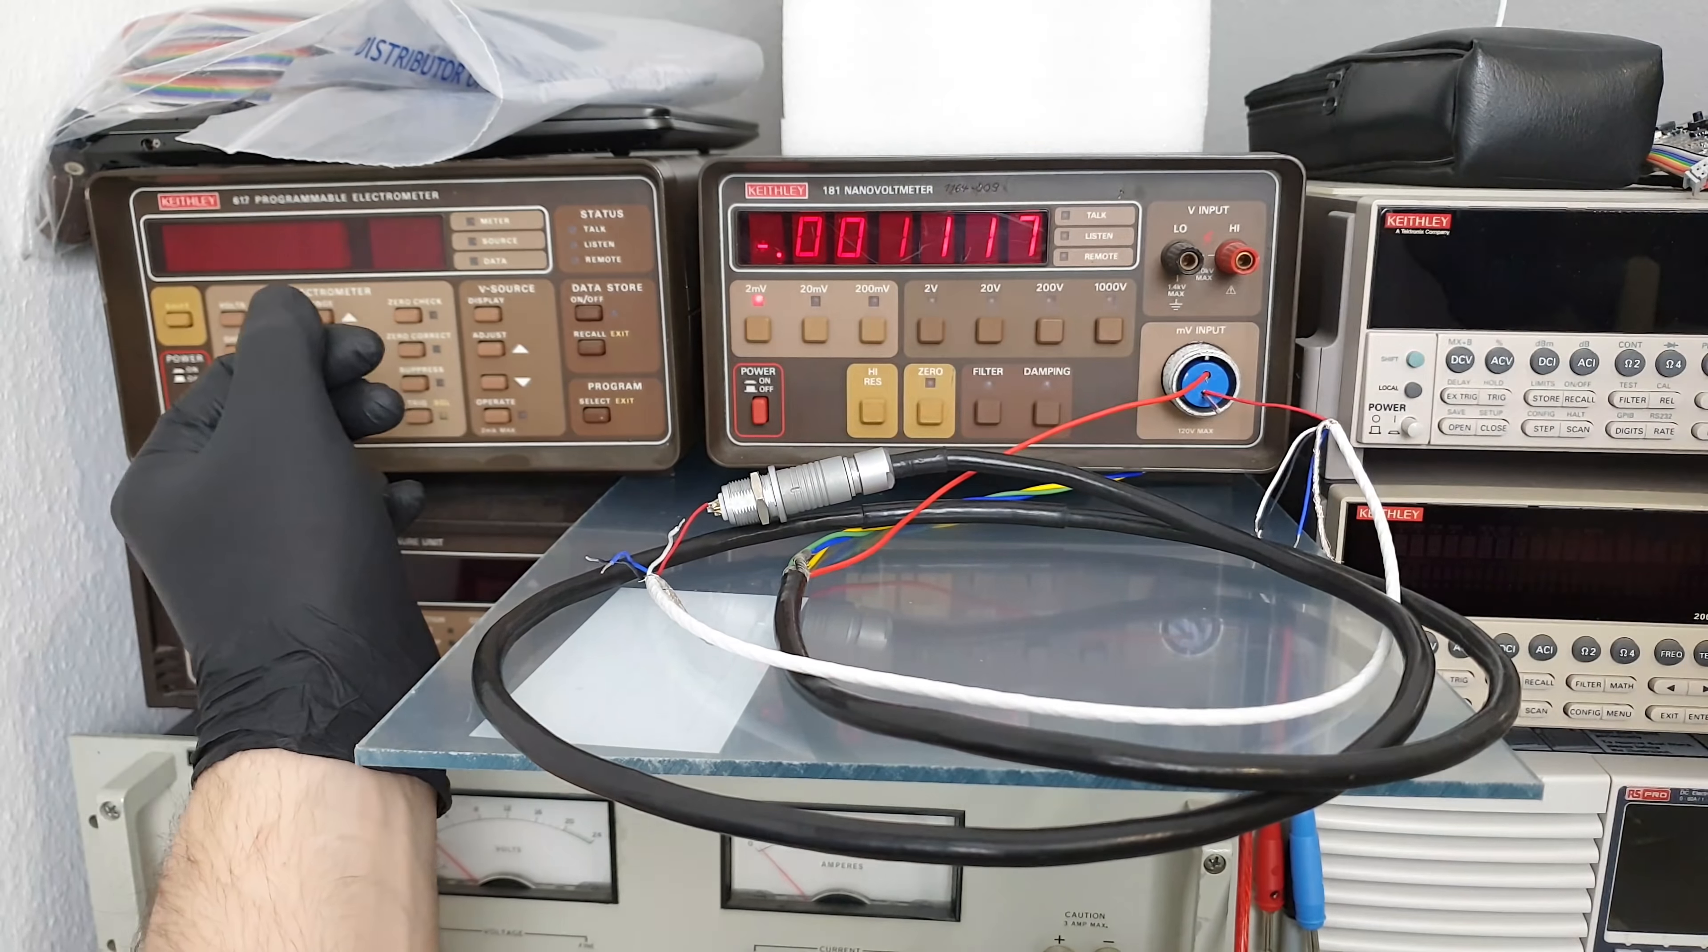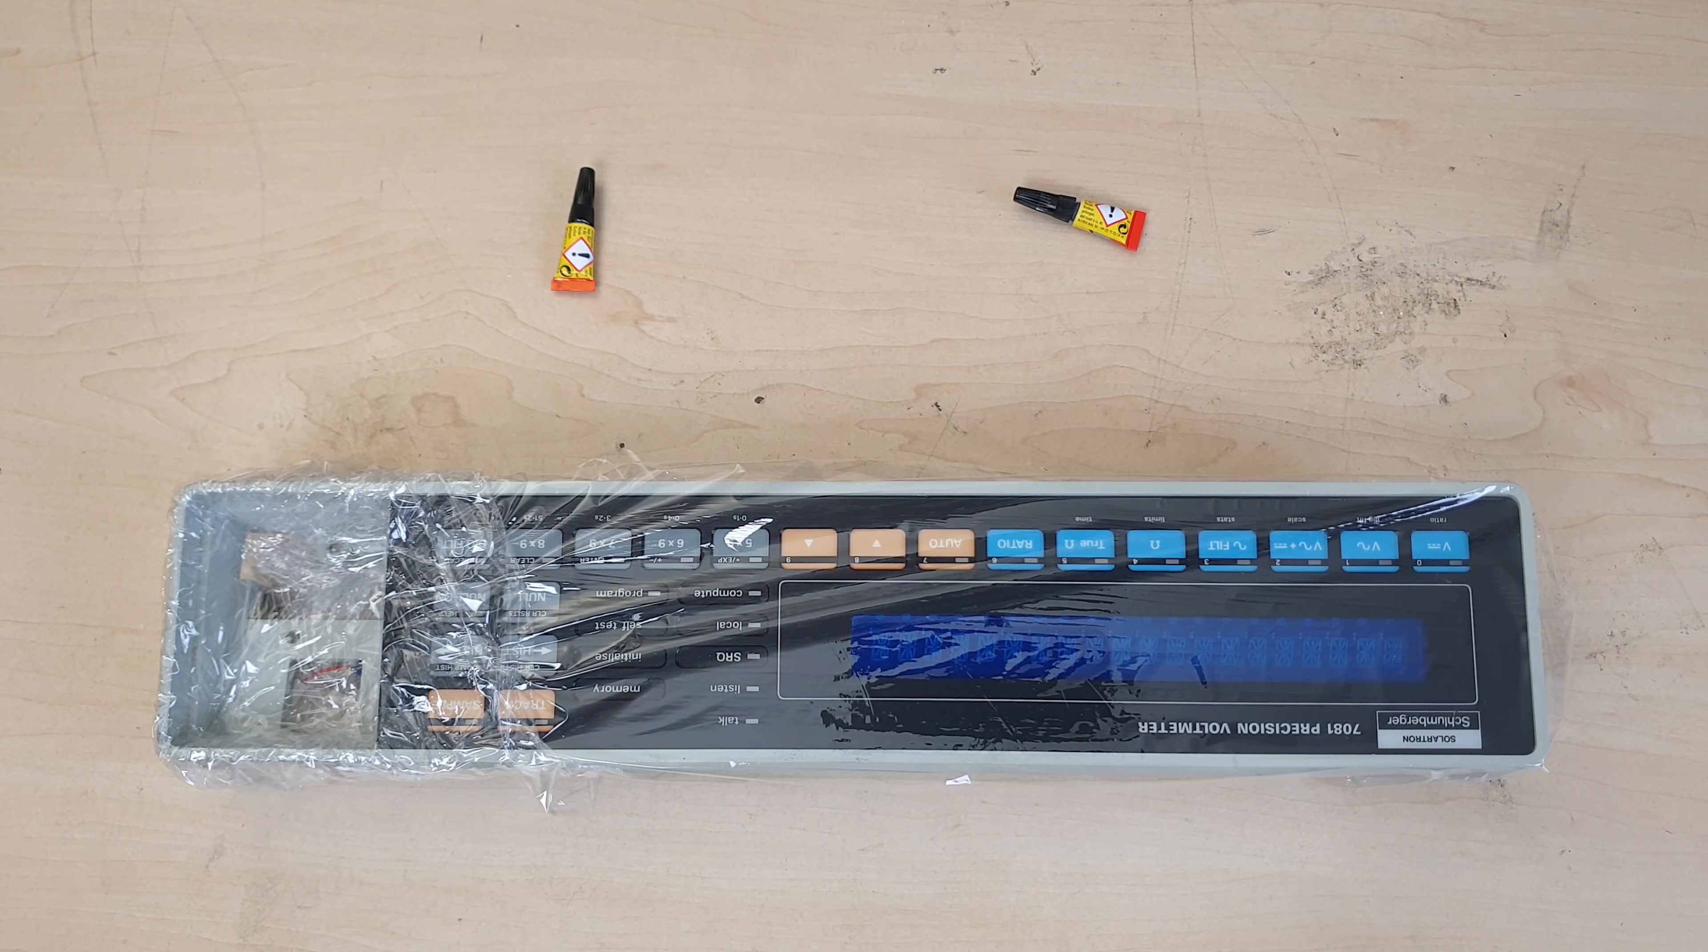This connector area is just an insert very lucky. I only just realized that I've shown this exact same measurement before in the Keithley 181 video, so chances are that some of you may have forgotten too. Here's a quick refresher. Solartron original input cable, unwanted microvolt offset in spite of luxury Swiss made Fischer connector. Not very good. These are Pomona 3770 low thermal EMF binding posts, directly gold plated tellurium copper, no evil nickel layer in between. Those would be a perfect match for this instrument, I only have to find a way to fabricate a new insert.